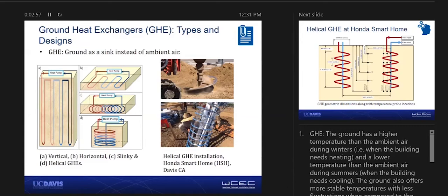Ground heat exchangers come in a variety of designs and configurations, the vertical GHE being the most common. The depth can be anywhere from 50 to 500 feet, but this design has its challenges. The excavation cost, usually the largest cost associated with installing these systems, is high as the depth increases. The depth of the GHE is also restricted due to geological as well as legislative constraints.